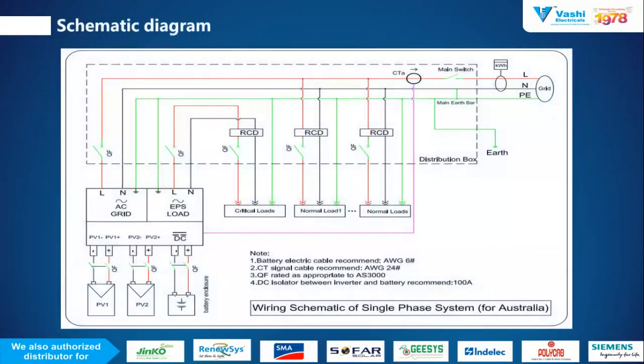This is the wiring diagram of the single phase hybrid inverter. The noticeable part is the connection of the critical load with the inverter. It's a higher priority load compared to the normal load. Whenever your grid is available, your critical load and normal load both are supplied from the grid, which means it is always connected with the grid.